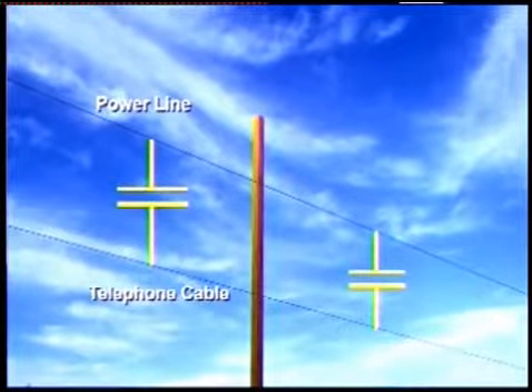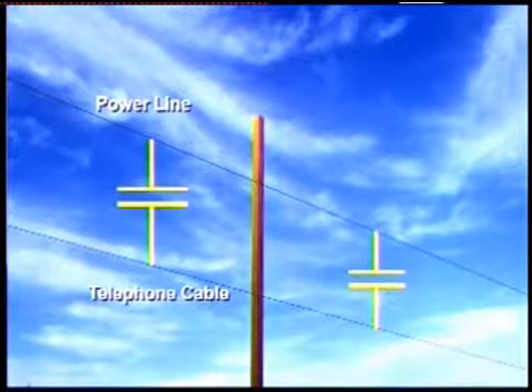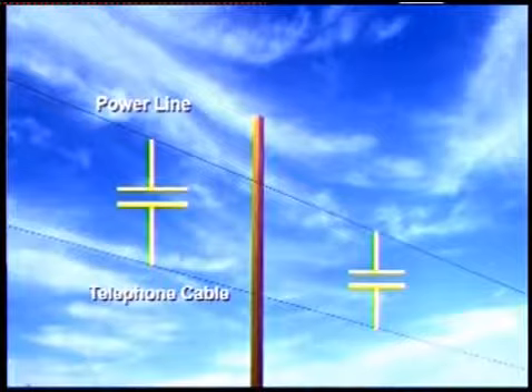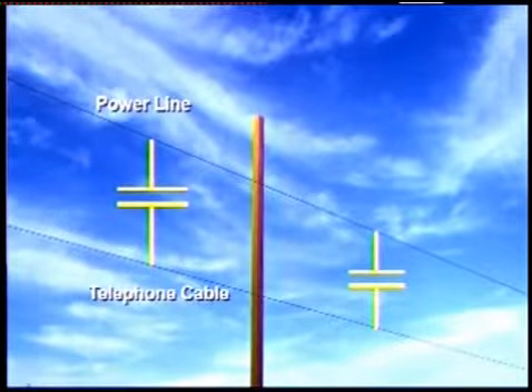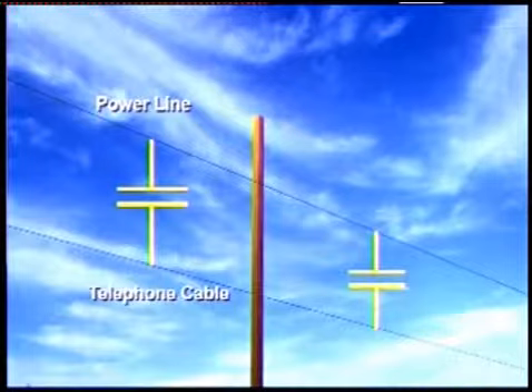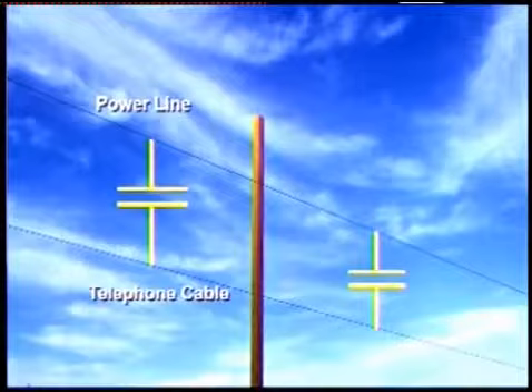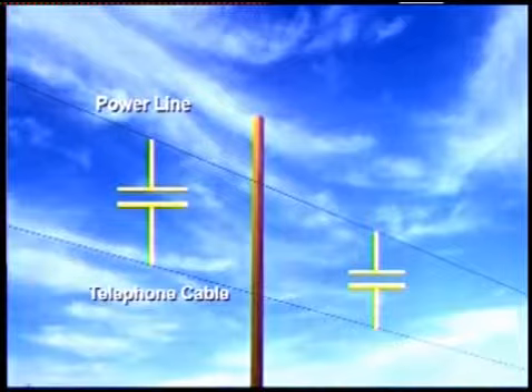Some AC will couple across any capacitance, as we saw at the site under the 230 kilovolt line. However, current flow through this capacitance varies directly with the amount of capacitance present and the operating frequency. At 60 Hertz, the frequency is low and capacitance is very low, so current flow must also be extremely low. Capacitive coupling at 60 Hertz then should not be considered a hazard.